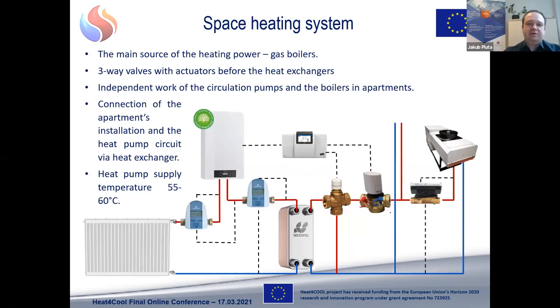Regarding the retrofitted space heating system, we have two separate circuits in two parts of the system in the building. The first circuit is between the heat pump and the heat exchanger, and the second part is the individual heating systems in apartments. We provided some modernization in the boilers and their circulation pumps work. The circulation pumps inside the apartments are now controlled by a separate controller based on the indoor temperature, and it allows us to work the heating installation in apartments without need of the gas burner work. Of course, if the heat provided by the heat pump is not enough for the apartment, then the gas burner will start and it will start the gas consumption.